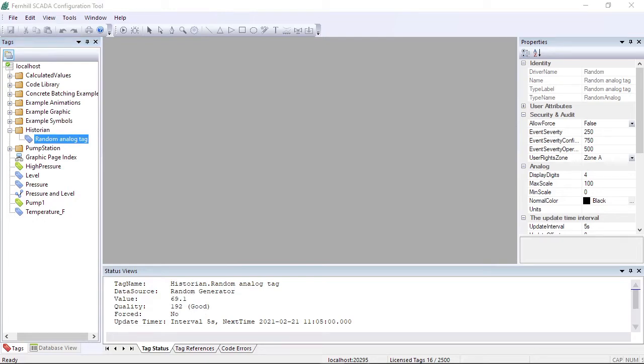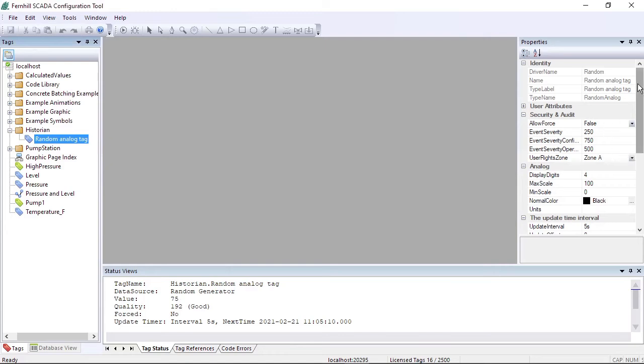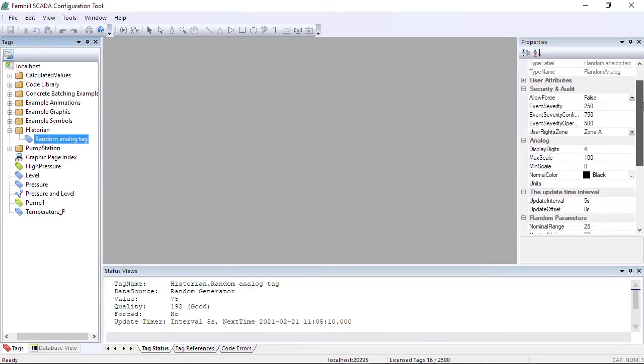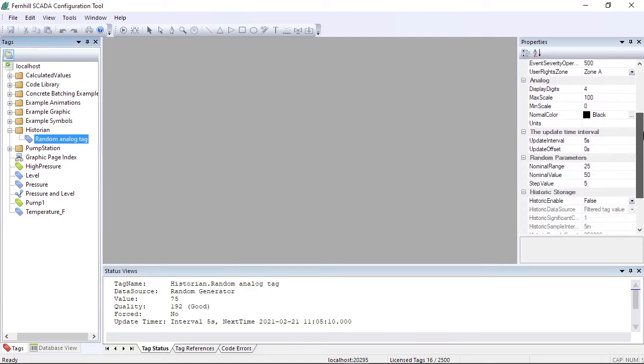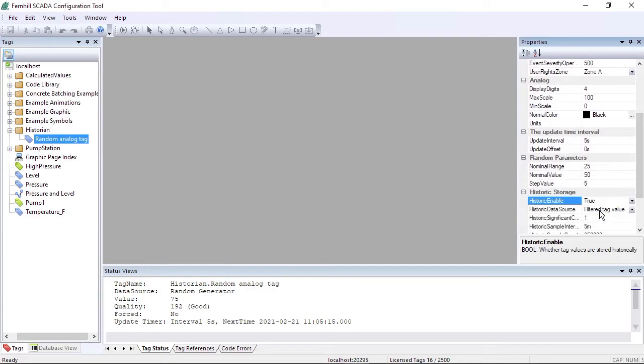Let's say we want to store the value of the tag we just created historically. To do this in Fernhill SCADA we make sure the tag is selected in the tag window, then in the properties window we set historic enable to true. And that's it. Once we set historic enable to true, the Fernhill SCADA historian will store samples for the data point tag.